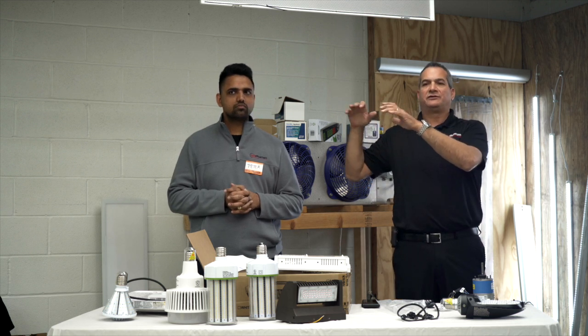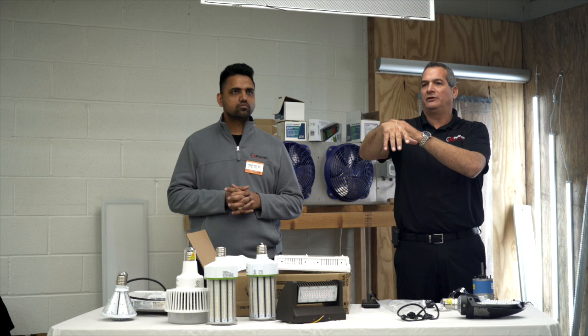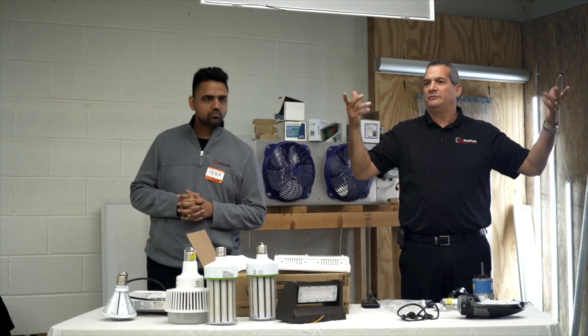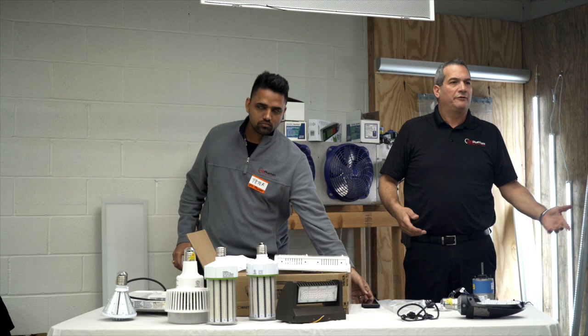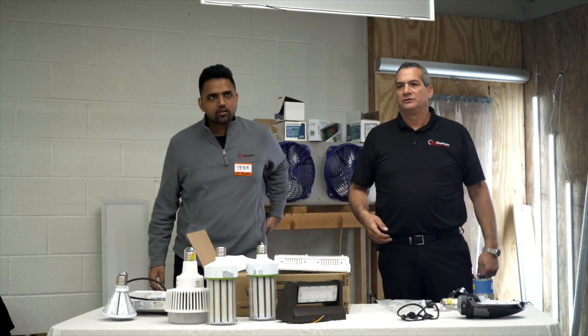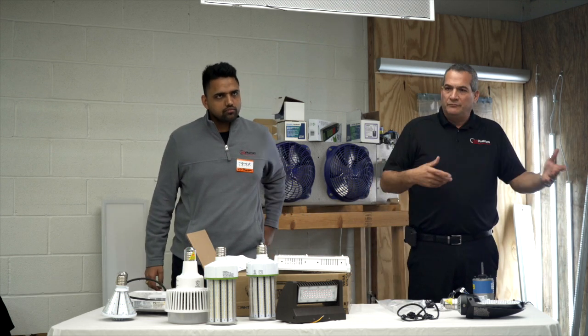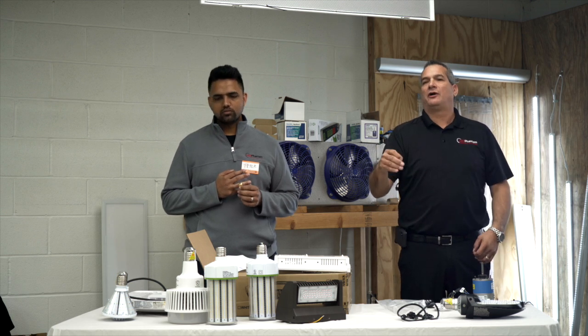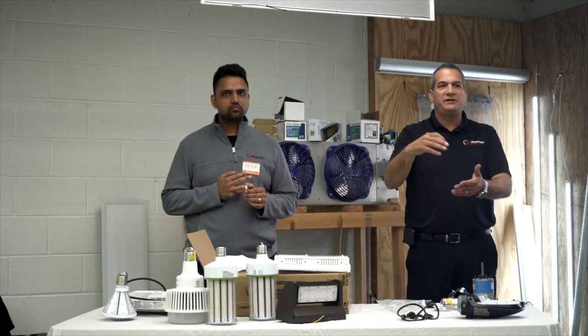You can never turn the stairwell light off completely; there always has to be some light on in the stairwell. This is a solution instead of buying a fixture that has a separate light inside it that turns on when there's no occupancy and shuts the main light off. With this, you can just use that one light and simply program it to only shut down to 30%, still meeting the stairwell code. So there are codes you can actually meet without having to go out and buy these specific fixtures. When you have to buy a specific stairwell fixture, you're paying $300-400 for what's basically a $100 fixture just because it says stairwell. So this beats that. This should help you be a little bit more flexible with our basic fixtures.